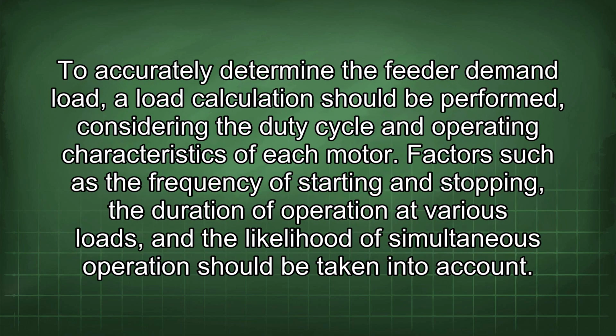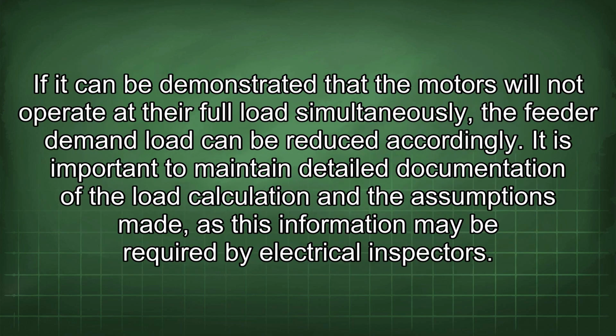To accurately determine the feeder demand load, a load calculation should be performed, considering the duty cycle and operating characteristics of each motor. Factors such as the frequency of starting and stopping, the duration of operation at various loads, and the likelihood of simultaneous operation should be taken into account. If it can be demonstrated that the motors will not operate at their full load simultaneously, the feeder demand load can be reduced accordingly. It is important to maintain detailed documentation of the load calculation and the assumptions made, as this information may be required by electrical inspectors.